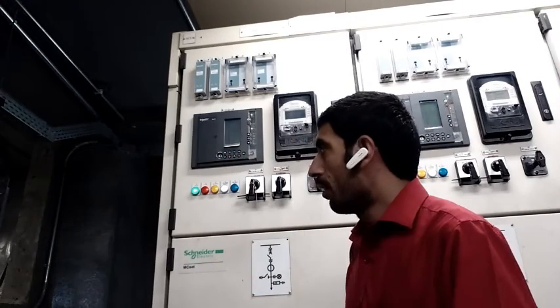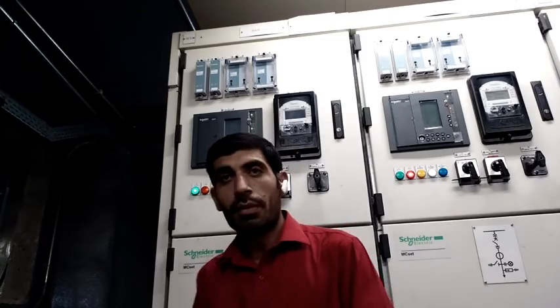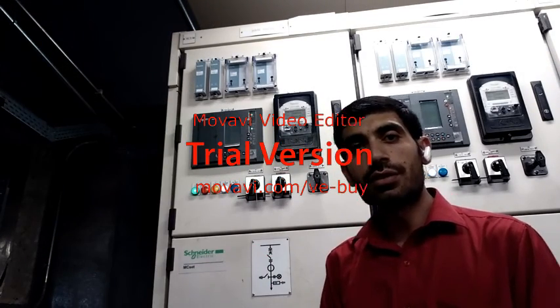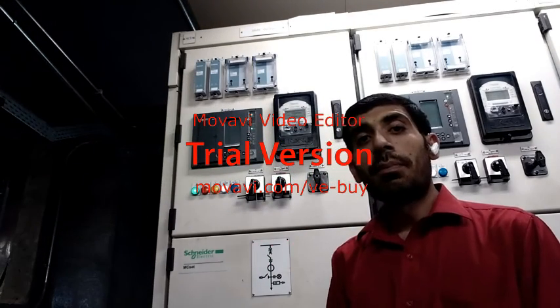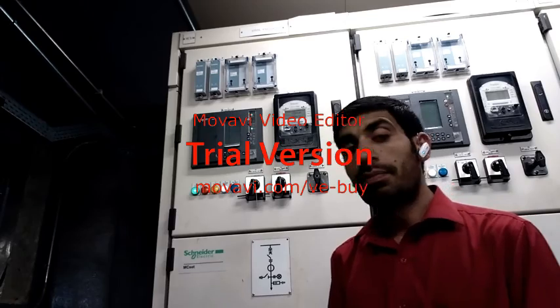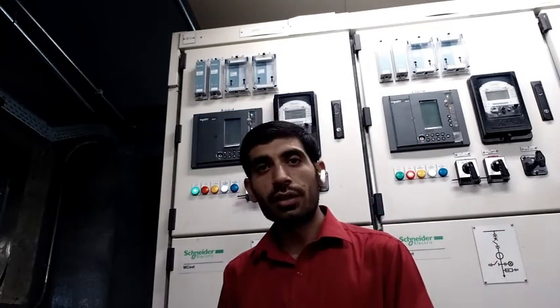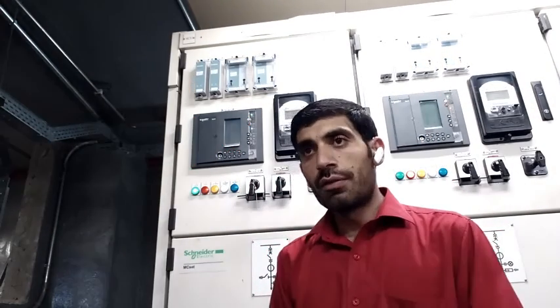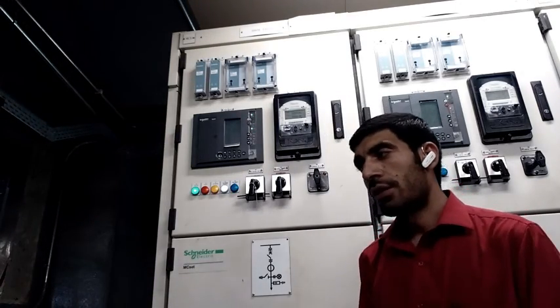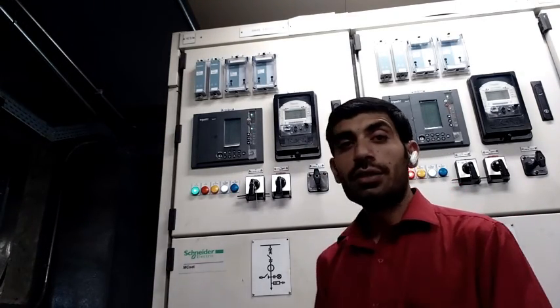And for example, my bus CT is 600 by 1 amp. The rated value of the CT is 600 by 1 amp. If my primary side is 600 ampere, my secondary side should be 1 ampere. And the same thing for VT values. If my primary side is 13.8 kV, my secondary side will be 115 volts.